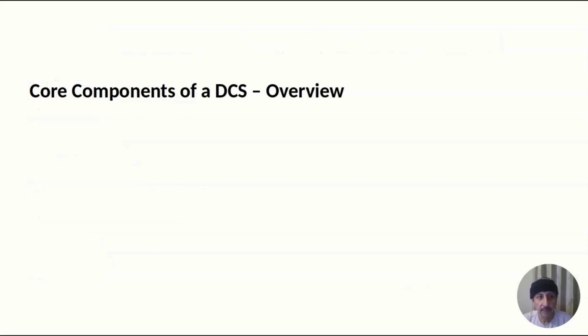Core components of a DCS. A DCS isn't a single box, it's an ecosystem. Four core components inside it work together. First, the controllers, the brains that run the control logic. Second, I/O modules, the sensory and motor interface with the physical world. Third, operator stations, also called HMIs. HMI is the acronym for Human-Machine Interface, where humans interact with the system. And fourth, the communication network, the nervous system tying it all together.